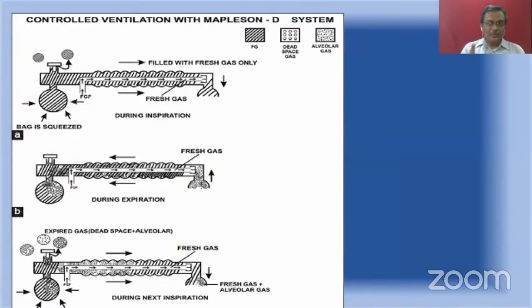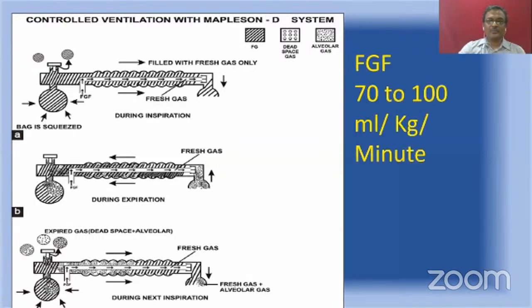I will show you the capnogram of a patient when Bain circuit is used. And during controlled ventilation, I said earlier, the fresh gas flow requirement is 70 to 100 ml per kilogram per minute. If the fresh gas flow is higher, the amount of carbon dioxide going to the patient will be less. If it is lower, more carbon dioxide will go back to the patient.